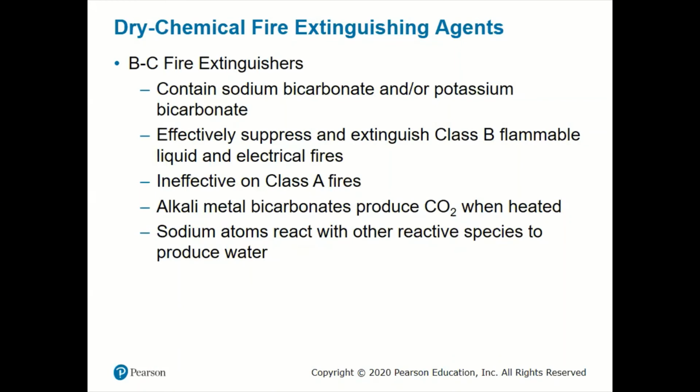Now, the BC fire extinguishers, the ones that are bicarbonate based, the way that these work is you get a couple of things. When they are heated, bicarbonate substances will decompose. And what they will decompose into are water and carbon dioxide. Carbon dioxide obviously works as a barrier. The water is actually somewhat ineffective because it's already in the vaporized phase. So its ability to absorb heat isn't that great.